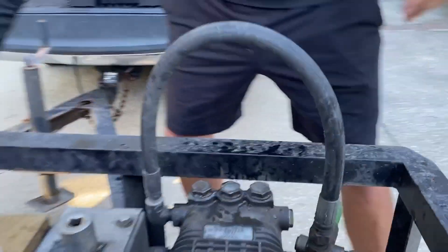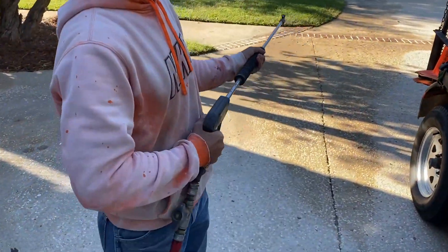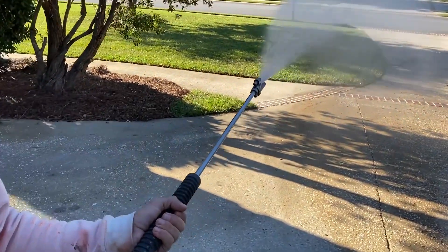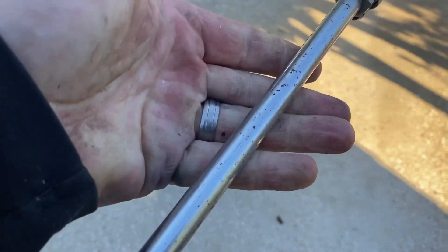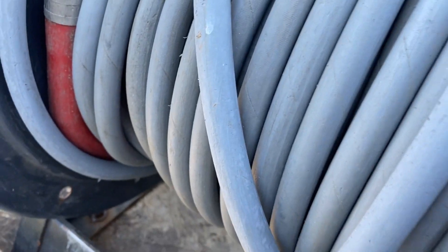All righty, so let's crank her up. Can you tell the difference? Oh yeah. It's back to normal. Good. No cavitation, it's not jumping. The hoses are not jumping anymore. So that was the problem.